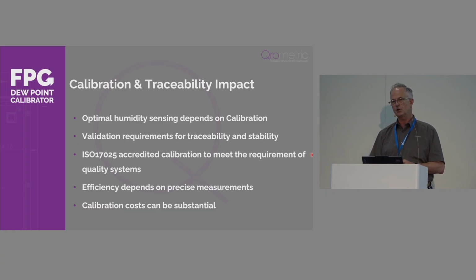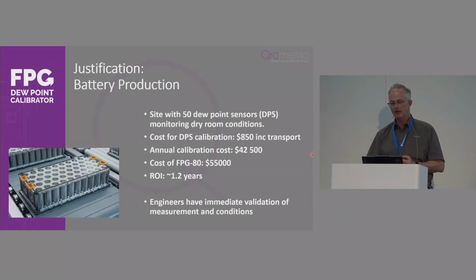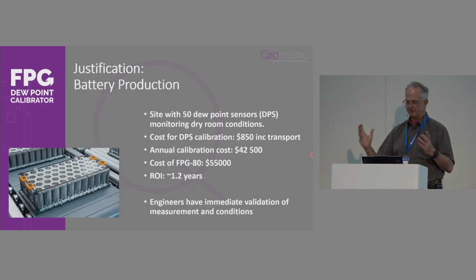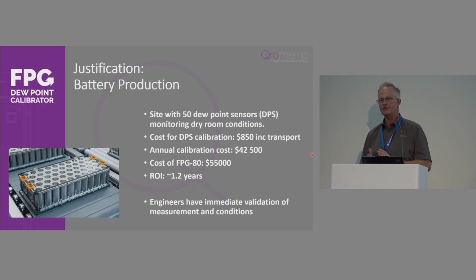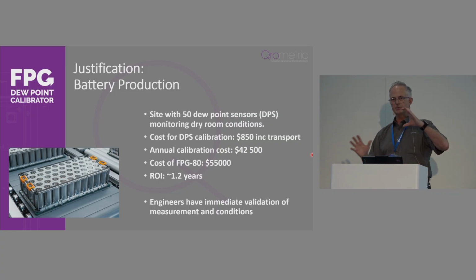And calibration costs can be very substantial. As an example, this is a real example from a real customer. We obviously are not going to say who it was, but they have about 50 dew point sensors on site. They're monitoring the battery production area, and they need to be sure that the condition is at a maximum of minus 40 degrees of dew point. So they have all these sensors monitoring the conditions to verify that condition, but obviously from time to time they see some changes.